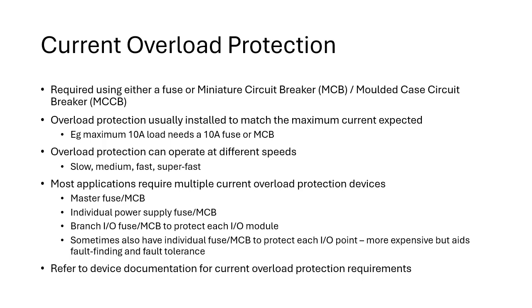So you can have overload protection which operates at different speeds. So if you're likely to see quite a long sustained overload when you first turn the system on, you might use a slow protection device. More likely you're probably going to use medium for most circuits. On the other hand, it might be that you really need to protect against anything above 10 amps, so you might want fast or even super fast overload protection. Just be careful of what the inrush is, because if you fit fast or super fast, then you might be overloading and tripping the fuse or the circuit breaker every time you turn the system on.